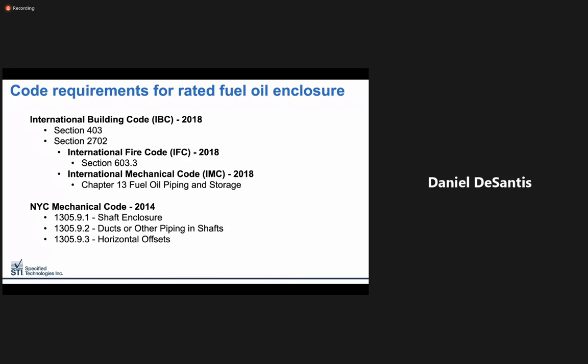Further breakdown of this code reveals that any fuel oil piping not located within the same room as the generator or storage tanks must be protected with a 2-hour minimum fire resistance rated assembly. Furthermore, codes like the New York City Building Code clearly stipulate that fuel oil must be in a dedicated shaft, or one that is not shared with any other services. This can cause some design complications because large MEP riser shafts in the core of the building would not be considered dedicated. Therefore, a shaft within a shaft would be required if those risers are used.